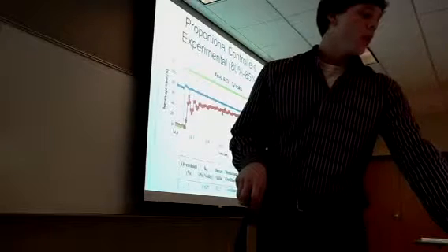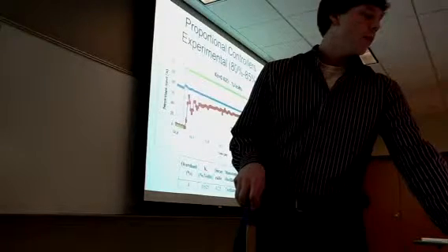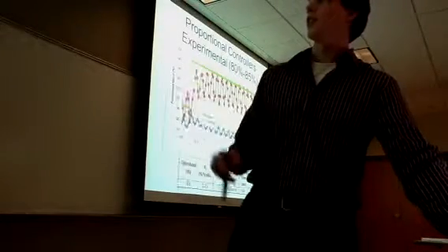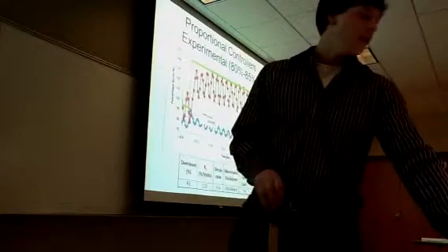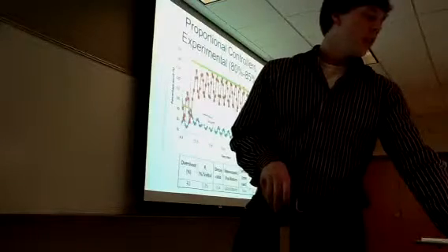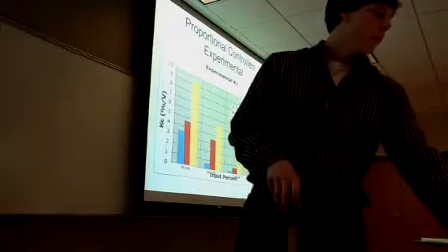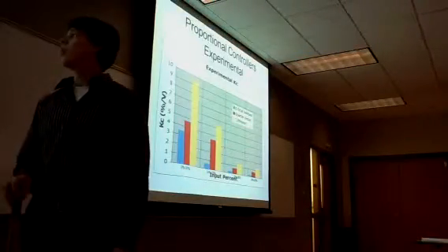This is for the quarter decay, and this is for the ultimate decay. And you see the oscillations never settle out, and you don't have a decay ratio. Here are the results for all of those regions for the proportional only controller experiments.